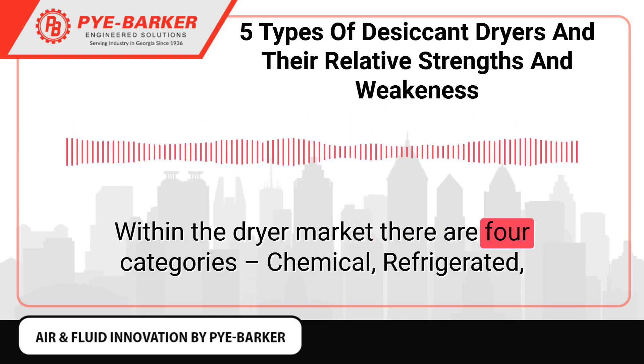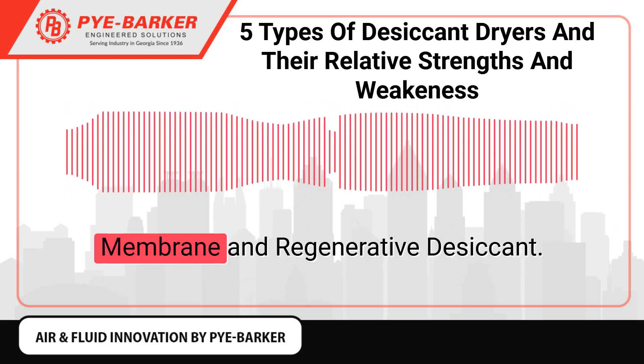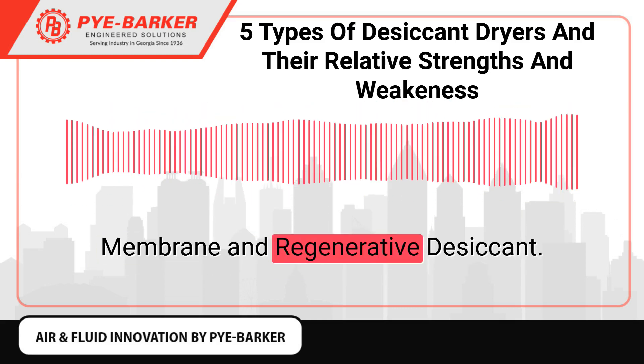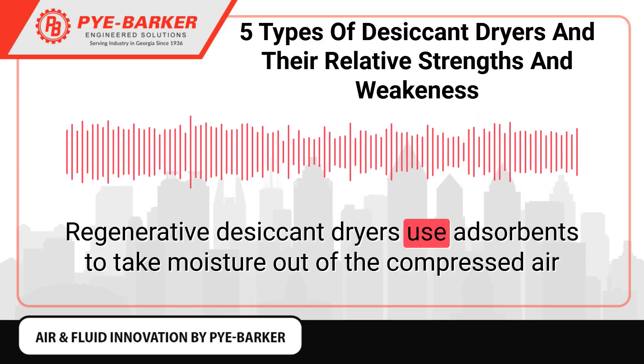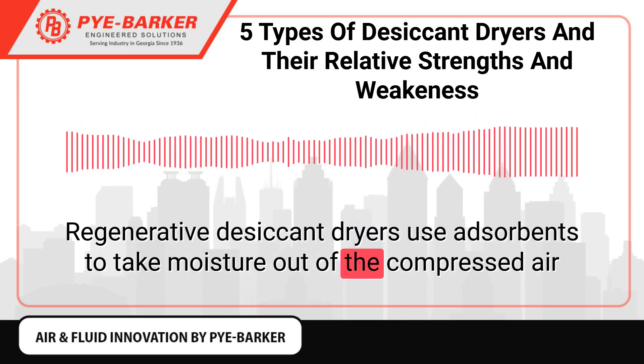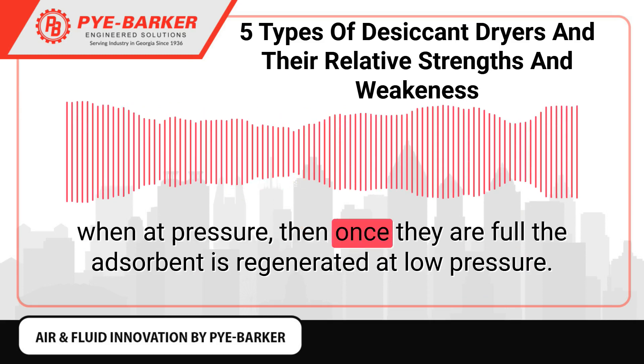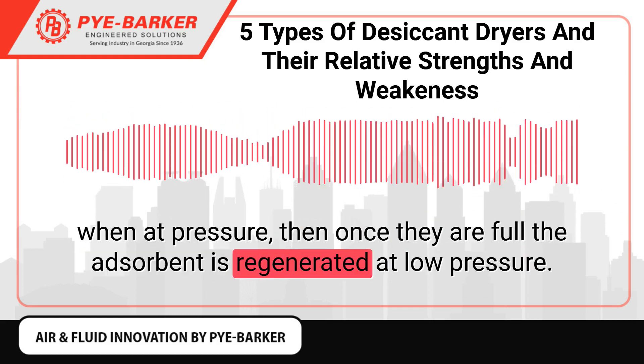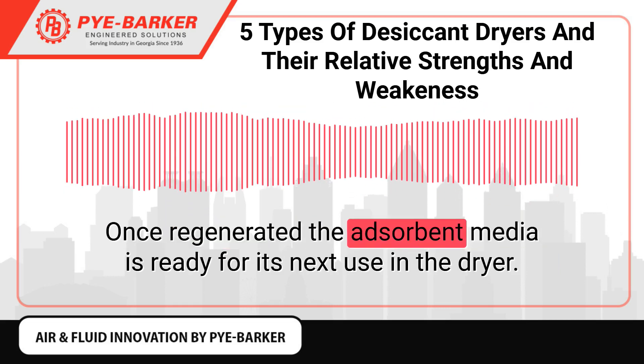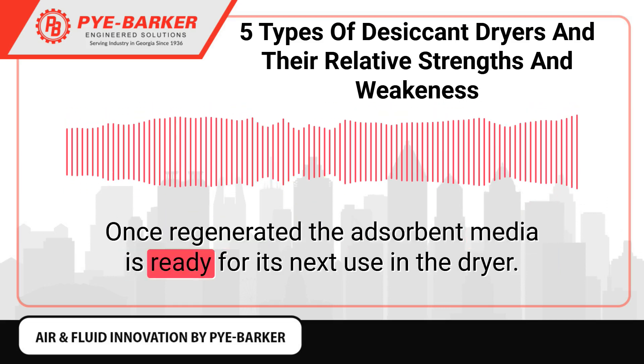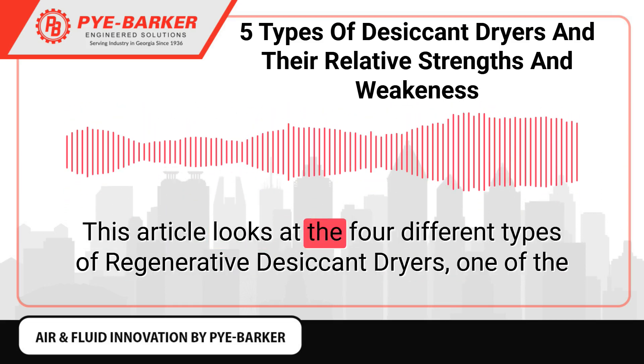Within the dryer market there are four categories: chemical, refrigerated, membrane, and regenerative desiccant. Regenerative desiccant dryers use adsorbents to take moisture out of the compressed air when at pressure, then once they are full the adsorbent is regenerated at low pressure. Once regenerated, the adsorbent media is ready for its next use in the dryer.